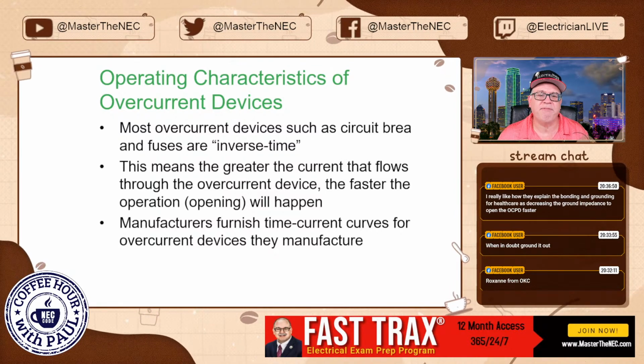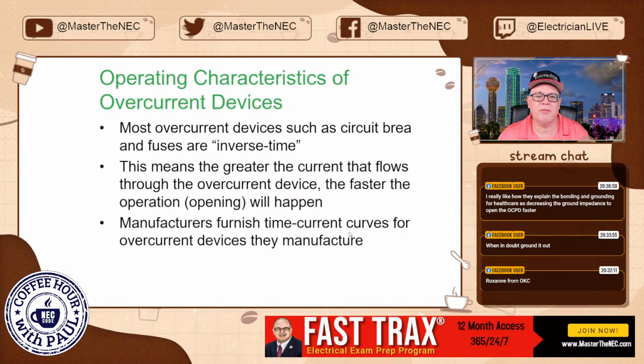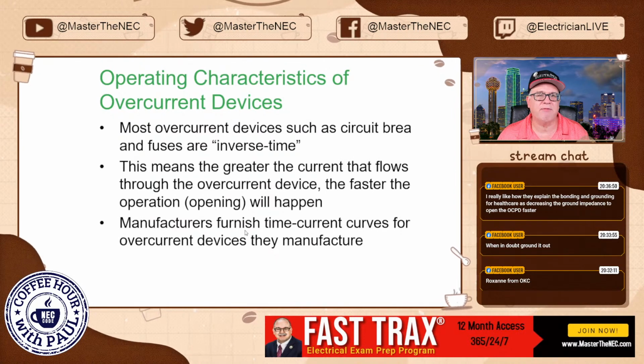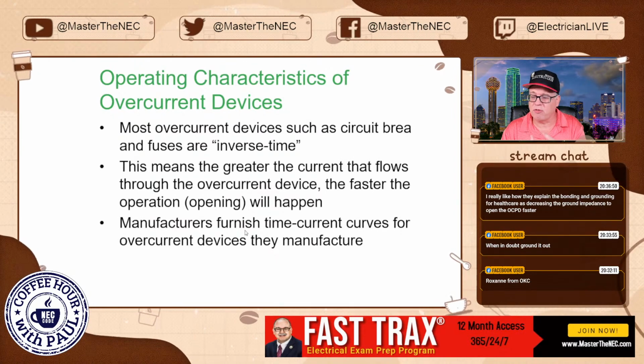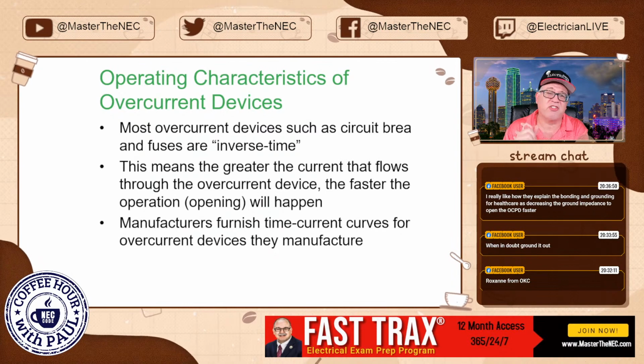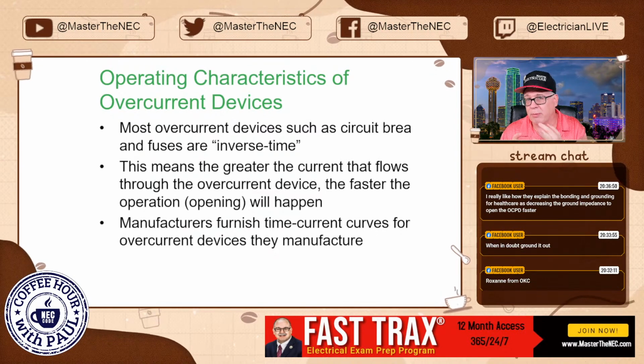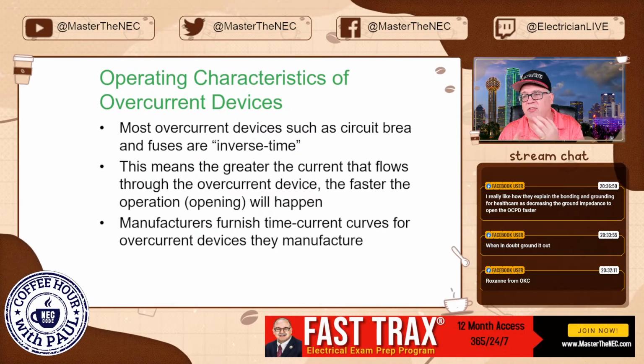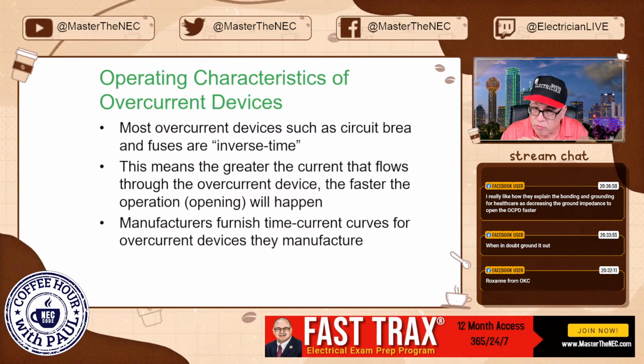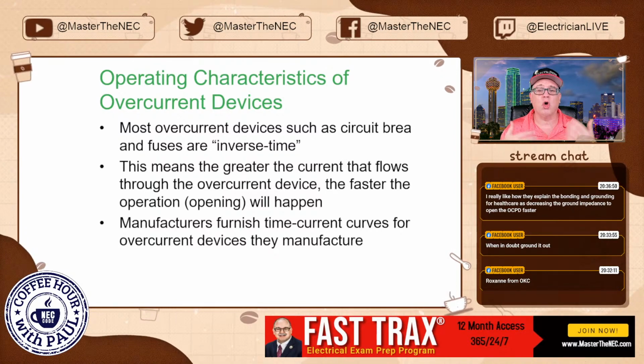Okay? Manufacturers furnish time curves of the overcurrent devices they manufacture. You can get them from your manufacturer. This is real important when you're doing things like selective coordination. We're dealing with healthcare facilities and systems where selective coordination is required. Then you're going to want these trip curves.